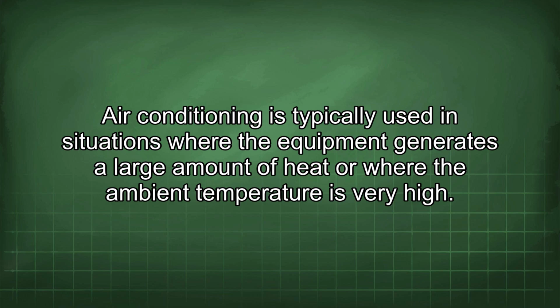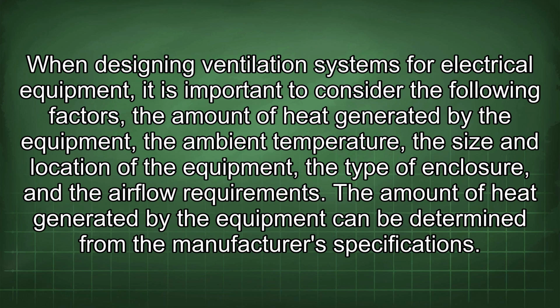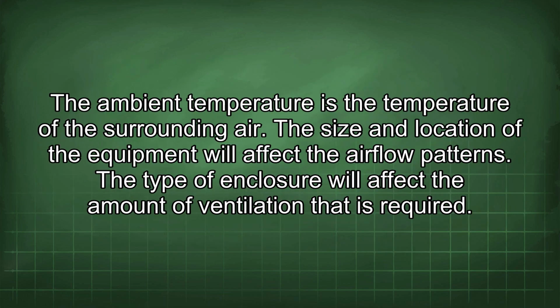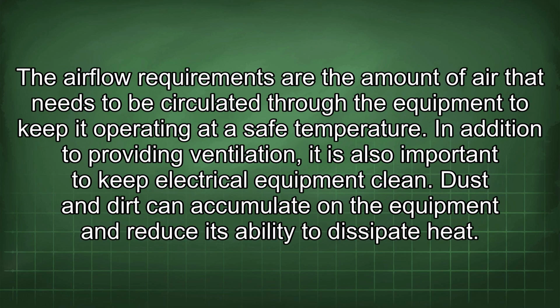temperature is very high. When designing ventilation systems for electrical equipment, it is important to consider the following factors: the amount of heat generated by the equipment, the ambient temperature, the size and location of the equipment, the type of enclosure, and the airflow requirements. The amount of heat generated by the equipment can be determined from the manufacturer's specifications. The ambient temperature is the temperature of the surrounding air. The size and location of the equipment will affect the airflow patterns. The type of enclosure will affect the amount of ventilation that is required. The airflow requirements are the amount of air that needs to be circulated through the equipment to keep it operating at a safe temperature.